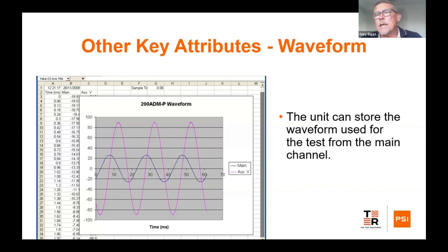So if you test a relay and you don't get the results that you're expecting, you don't really know whether or not it's the waveform that's causing the problem. With us, we have the ability to store the data and download that and look at the waveform. So if you're getting strange results, you can look at the waveform and say, yes, indeed, it is a sine wave that we're feeding it, and therefore the relay is out of specification. Or if the waveform was warped in any way, you'll know that the reason the relay test set is not testing correctly is because the waveform is not correct.